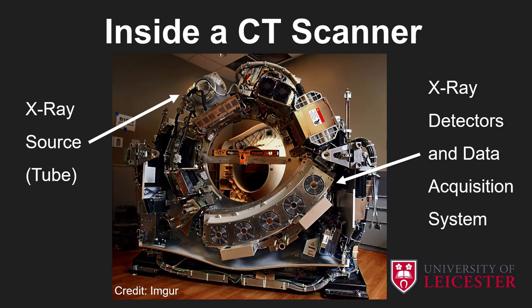Inside the scanner is clearly a much more complicated business. At the top you have the x-ray source or tube, with lots of equipment to support it, cool it down, and supply it with a very high voltage. X-rays are produced there, they travel in a straight line through the centre of the scanner to an array of detectors and the data acquisition system, where the first stages of image production occur. This whole gantry spins around the patient at very high speed.